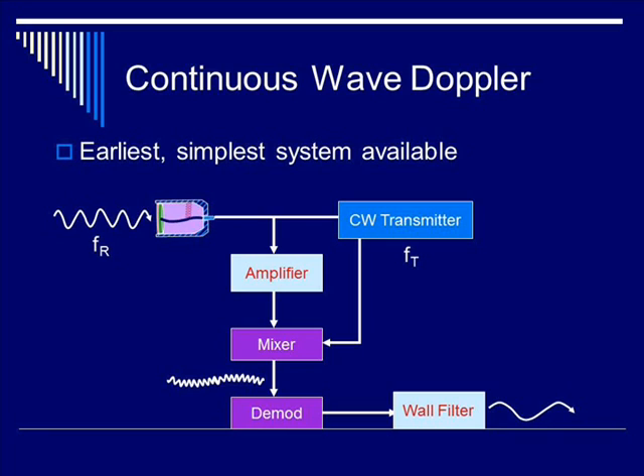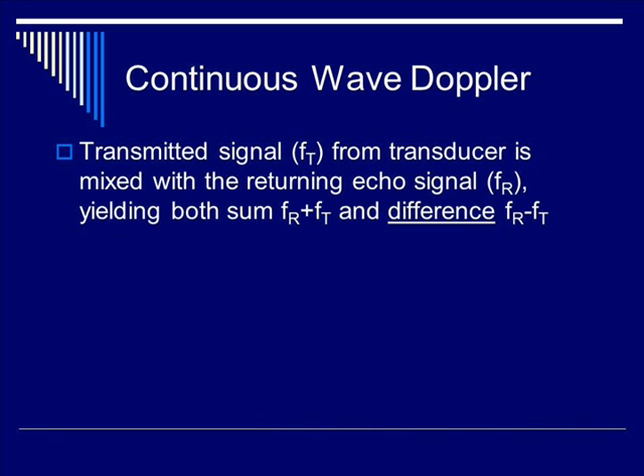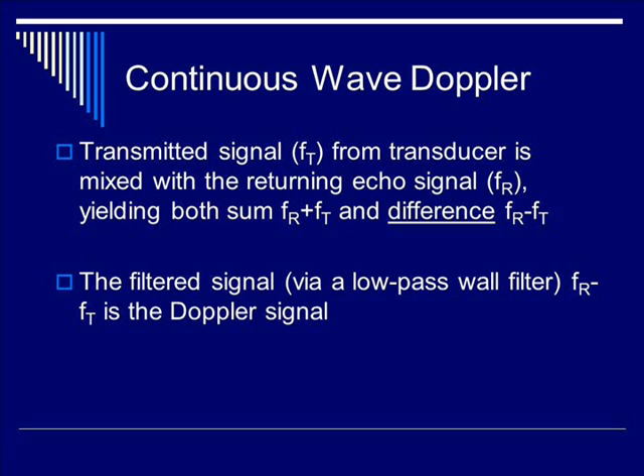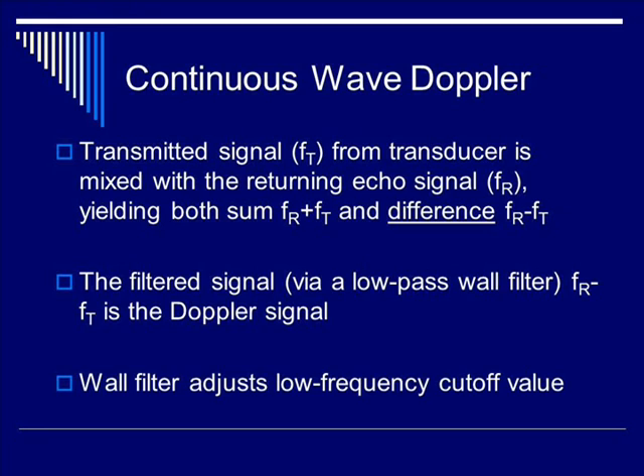In review, you have the transmitted frequency and the received frequency multiplied together, giving both the sum and the difference of the two. The demodulator gives you only the difference. The transmitted signal f(t) from the transducer is mixed with the returning echo signal f(r), yielding both sum and difference. The filtered signal via the low-pass wall filter — f(r) minus f(t) — is the Doppler signal. The wall filter adjusts this low-frequency cutoff value.